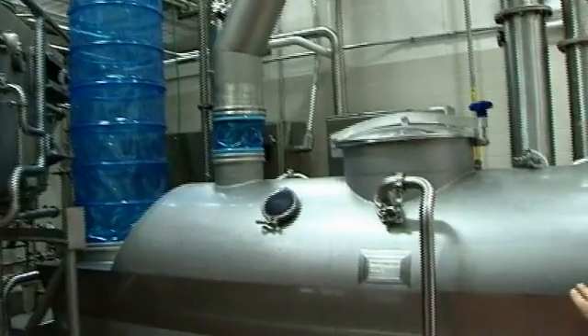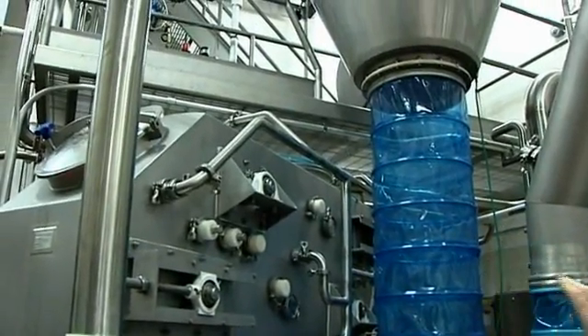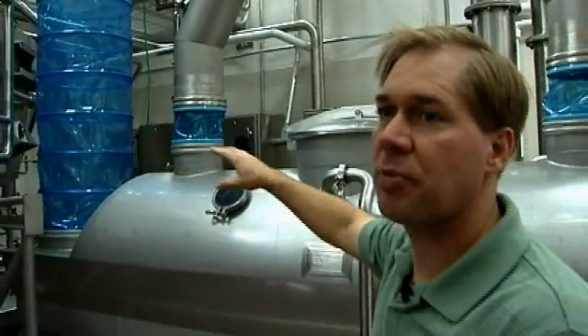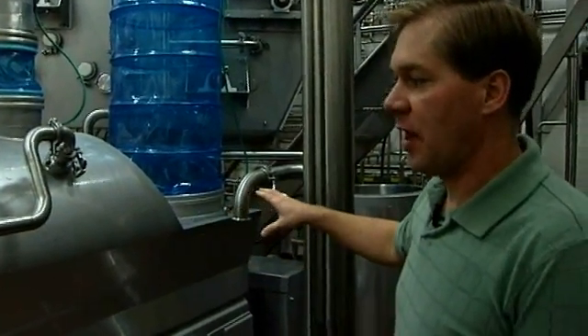From the primary drying chamber, we have two possible paths. Currently, the powder falls directly out of the primary chamber into our vibrating fluid bed dryer for the second stage of drying. We also have the option to utilize a timing belt placed underneath the primary chamber, where the powder goes through the timing belt before being dropped into the fluid bed. If we want to make non-hygroscopic whey products, the timing belt is used to crystallize the lactose prior to secondary drying in the vibrating fluid bed. The vibrating fluid bed dryer has three separate zones — two for heating and one for cooling — and also gives us the ability to produce instantized dairy ingredients.